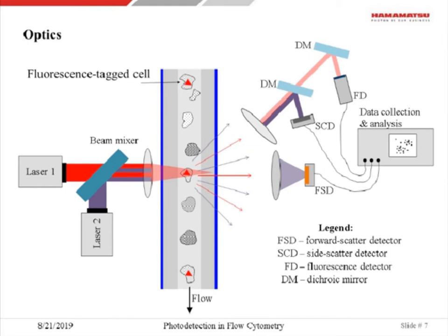Let's look at the basic setup of the optics. We have a flow cell with at least one, typically more, lasers that provide illumination of the cells. One laser illuminates the cells, while other wavelengths may be necessary to excite fluorescence. The light interacts with the cell and undergoes various processes. Around the cell, we have two optical system sets: forward scatter, which detects light scattered by a relatively small angle in the forward direction, and side scatter at around 90 degrees, which detects light scattered by a larger angle.